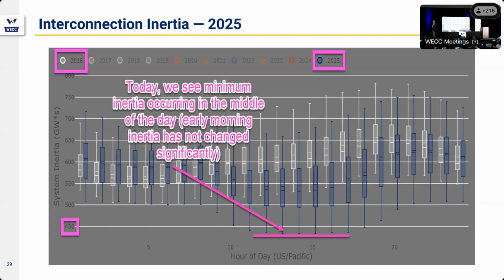So we've seen a reduction in our minimum inertia of about 10%, 450 gigawatt seconds, down from 500 gigawatt seconds. But the most dramatic thing is it's happened in the middle of the day. Our minimums in the early morning really haven't changed, and that's because we're serving the same load with synchronous generation early in the morning.